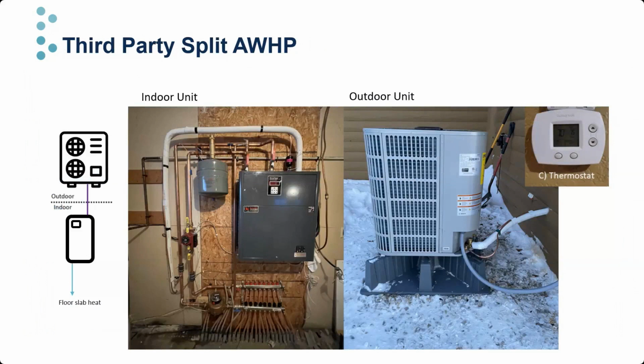Here is what a split system looks like. Both of these images are from Site 2 in Garfield. The ODU is literally a commercially available air source heat pump compressor unit. In this case, it's a Bosch Bova outdoor unit as shown in the right picture. And if you weren't sure about air-to-water heat pumps just being ASHPs, I hope this puts you at ease a bit. Because if I only showed you the image on the right with no context, you probably wouldn't be able to tell whether this is an air-to-air system or an air-to-water system.